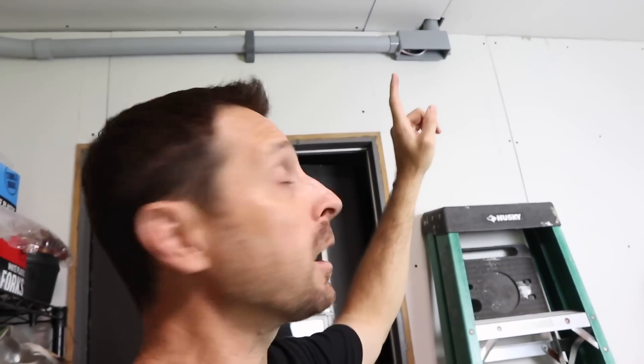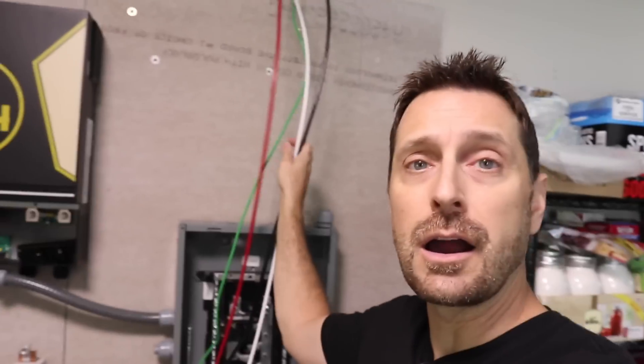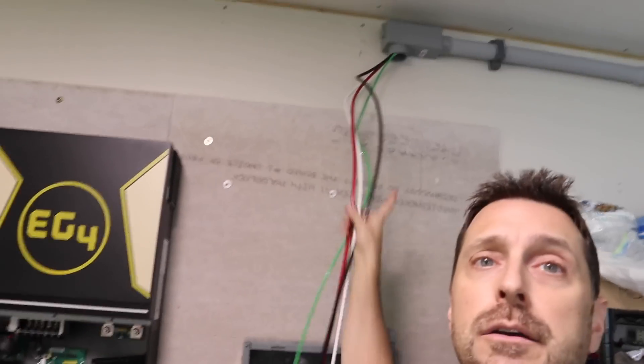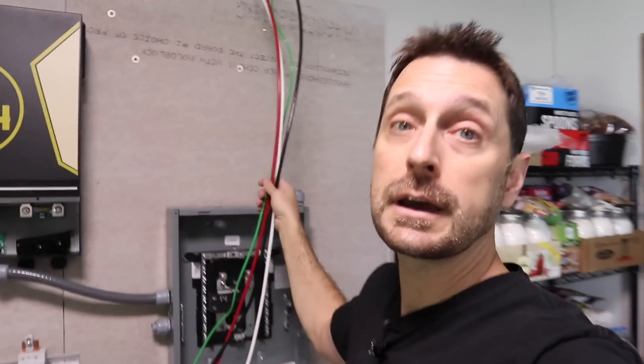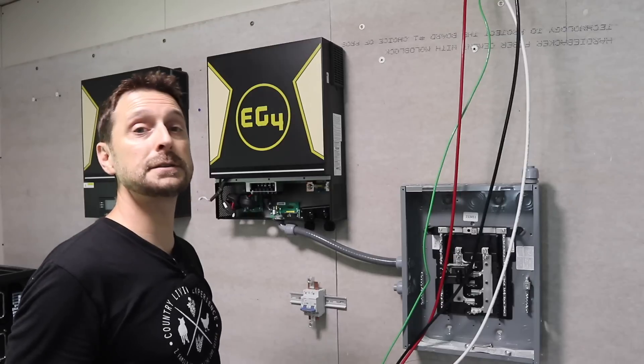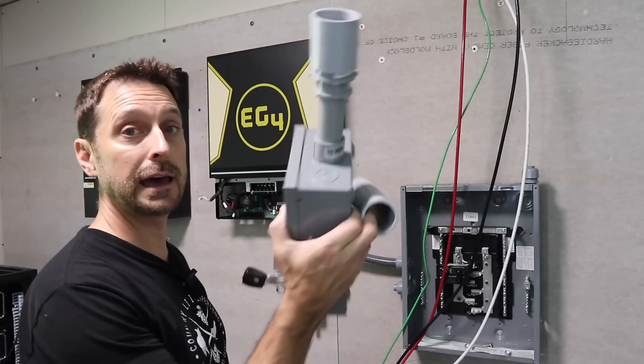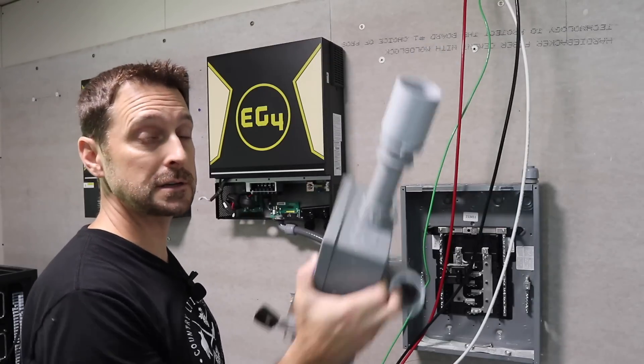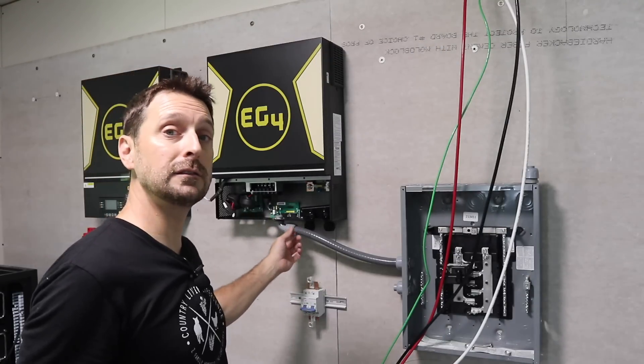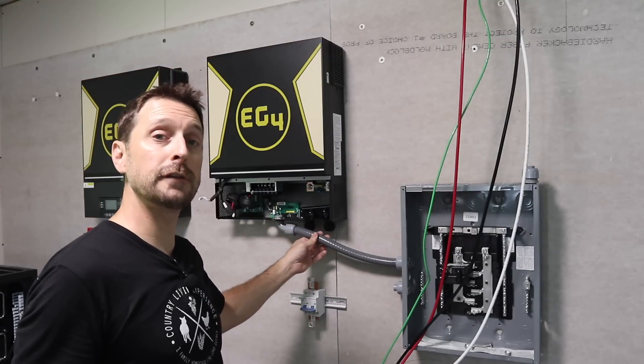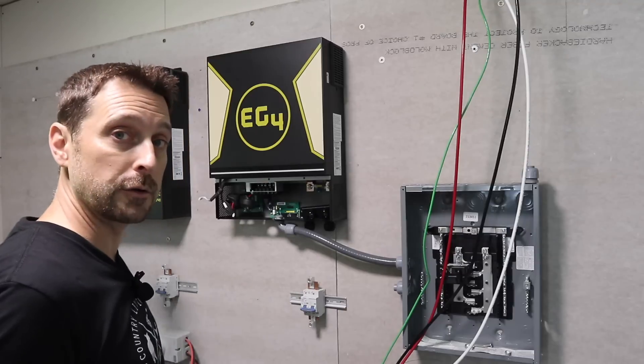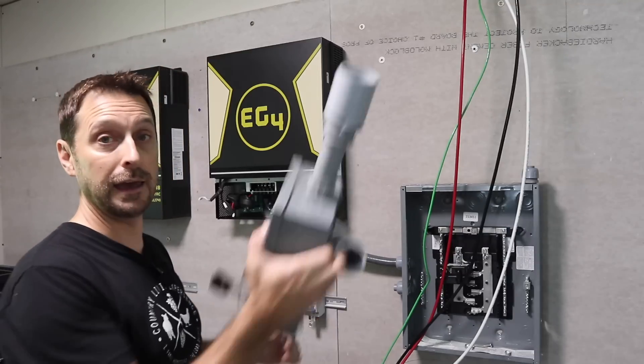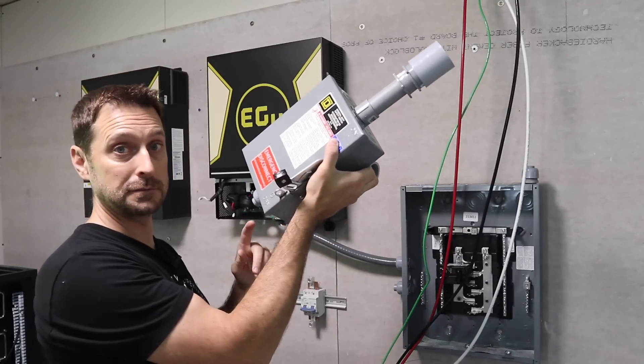We had a nice cool day the other day and we ran our four gauge through our conduit in our attic and we cut back our original conduit to accommodate for this new setup on the wall. First things first we need to add our safety switch and then we need to add more flexible conduit for our other inverter and the safety switch.